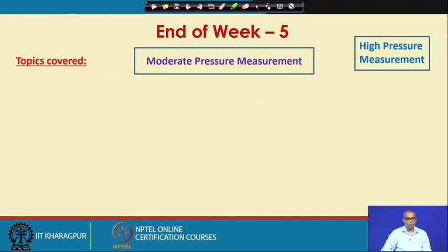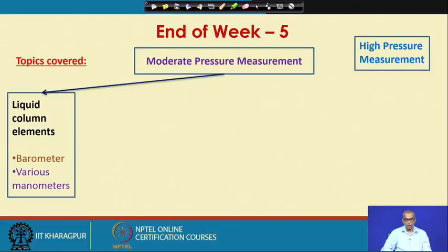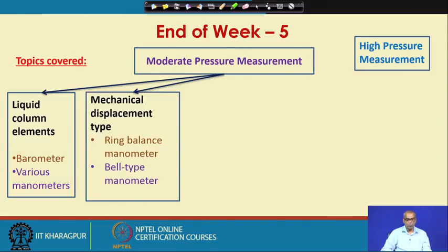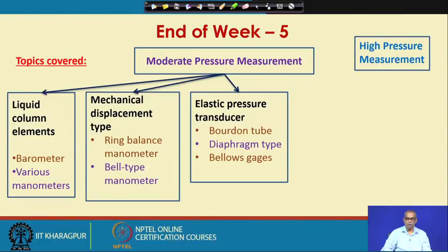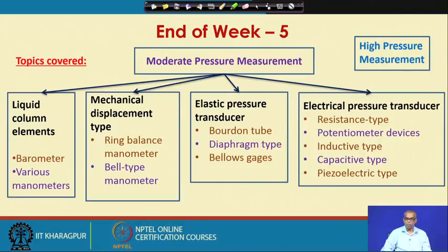So, this is the end of week 5. The topics that we have covered are moderate pressure measurement as well as high pressure measurement. Under moderate pressure measurement, we have talked about barometers, various manometers which come under liquid column elements. We have talked about ring balance manometer, bell type manometer which comes under mechanical displacement type. We have talked about elastic pressure transducers such as Bourdon tube, diaphragm type, bellows gauges, and we have talked about electrical pressure transducers such as resistance type, potentiometer devices, inductive type, capacitive type, piezoelectric type. And then we also talked about high pressure measurement by manganin or gold chrome alloys through electrical methods. So, this is the end of week 5, and in the next week we will talk about measurement of very low pressures or measurement of high vacuum.